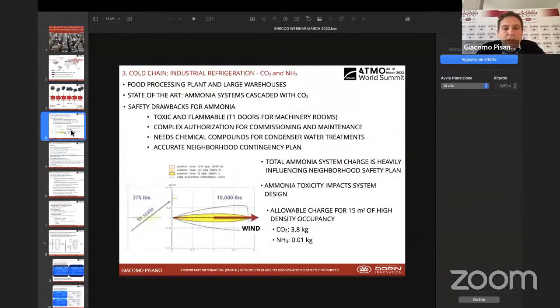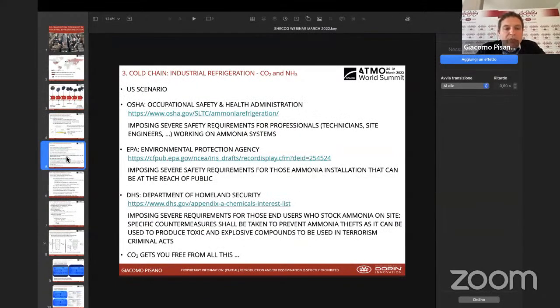Let's go a little bit more into the topic of today. It's a comparison between CO2 and ammonia in industrial refrigeration systems. Clearly, ammonia is a great refrigerant from a thermodynamic standpoint. It has some drawbacks, like every refrigerant. Some of the drawbacks of ammonia concern safety, due to toxicity and flammability of the refrigerant. So normally this brings some interest in alternative refrigerants to ammonia for large industrial applications. This is true worldwide. For instance, in the United States, there are several laws and guidelines that have to be followed from OSHA, from EPA, and from DHS, imposing specific regulations and safety requirements for ammonia systems.